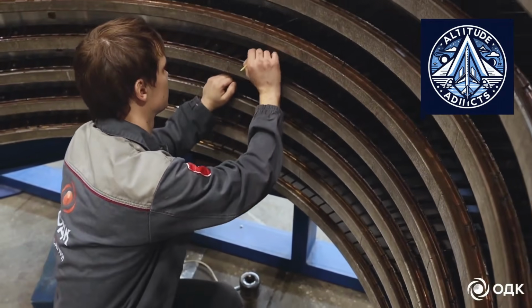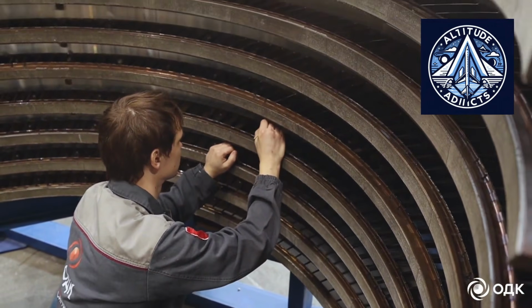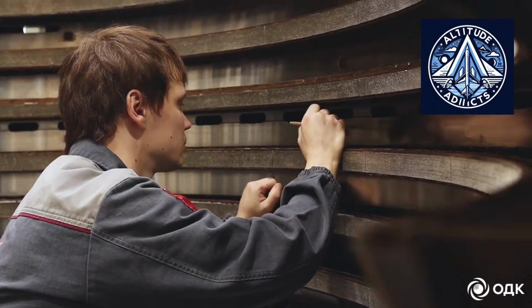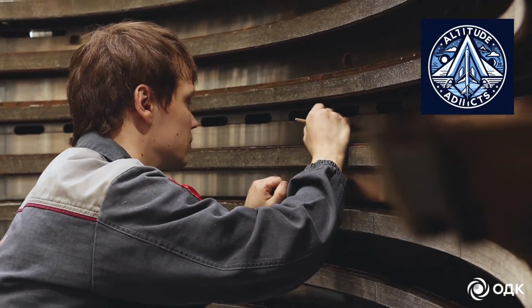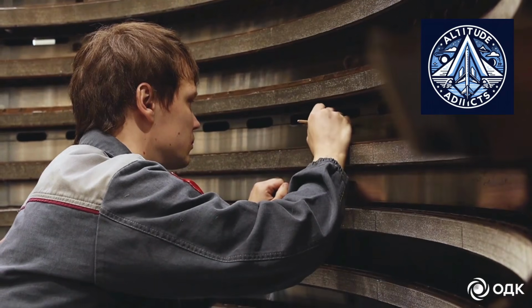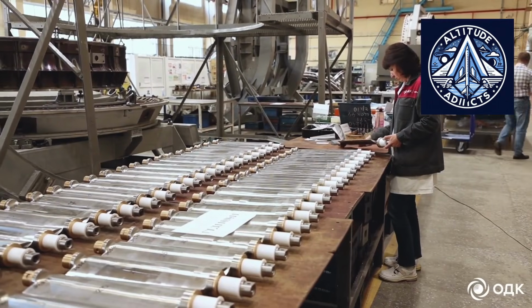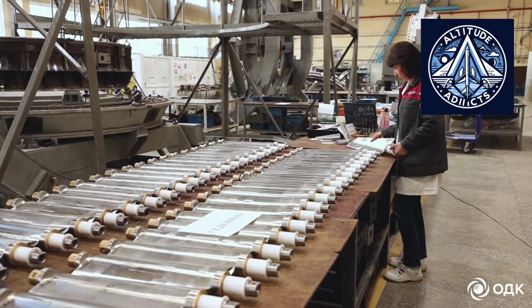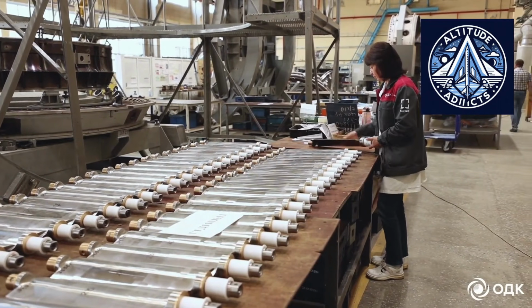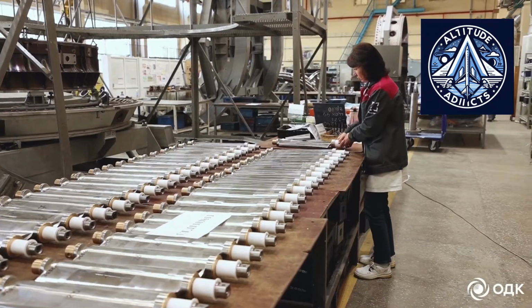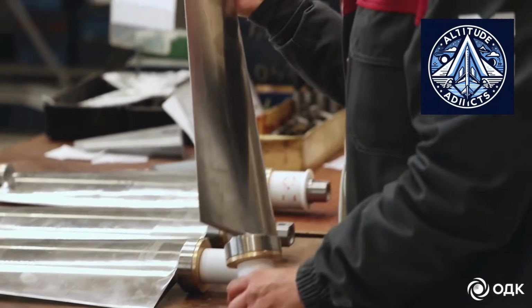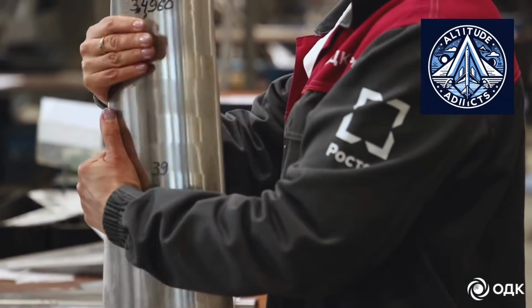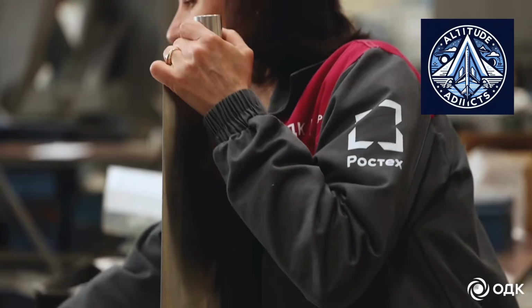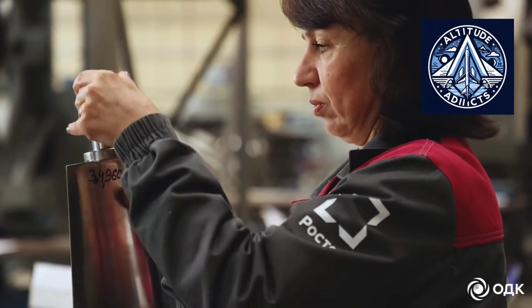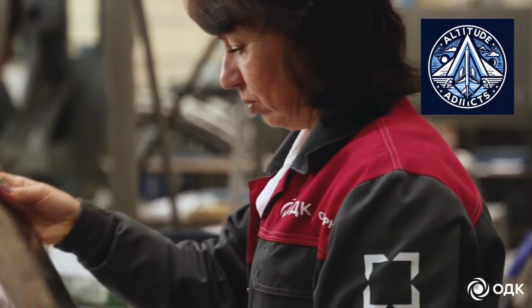The latest engine is the fourth GTD-110M model to be produced in serial production by Saturn, suggesting that the program has transitioned from prototype and demonstration phases to sustained manufacturing. Each turbine is subjected to an exhaustive acceptability testing program prior to delivery. Each unit generates its full rated output of 115 megawatts into the electrical grid while operating continuously on a dedicated test stand for 3 days, as per the United Engine Corporation.